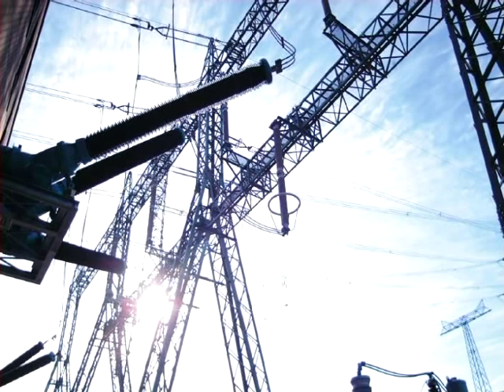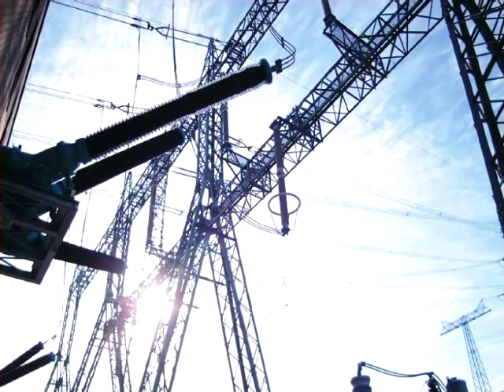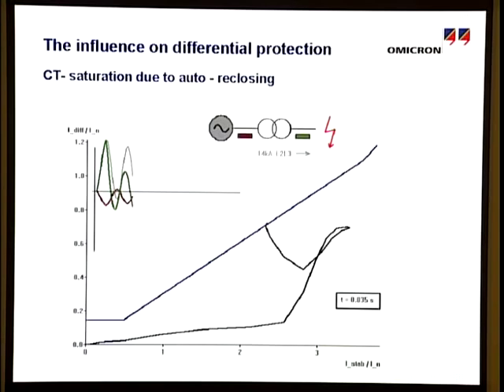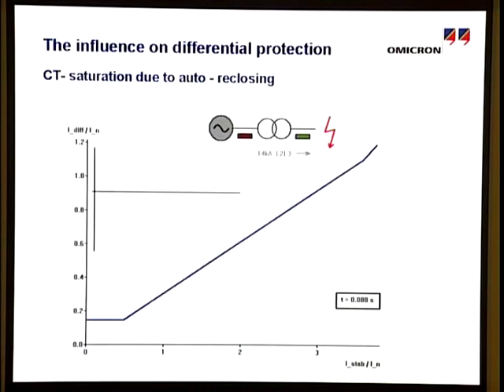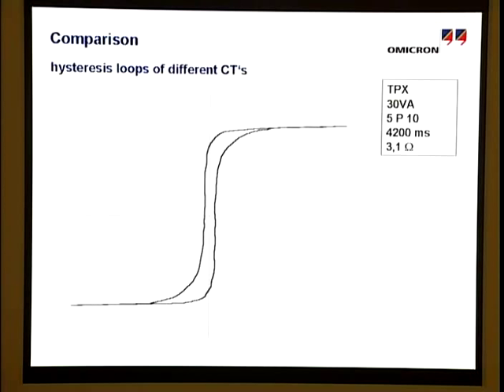Remanence — the ability to store magnetic energy — plays a role not to be neglected, especially with regard to auto-reclosing. As shown in the figure, a short circuit current of 14 kA with the first fault does not lead to CT saturation. With the unsuccessful re-closure, the CT is saturated due to remanence. If the relay behavior is also examined offline at re-closure, the simulation shows that the stabilizing characteristic is exceeded in the second area due to smaller stabilizing currents and considerably lower rise. Consequently, tripping of the differential protection is to be expected. Therefore, the iron core CT does not meet the requirements for this specific application if the tripping characteristic cannot be set to be less sensitive.